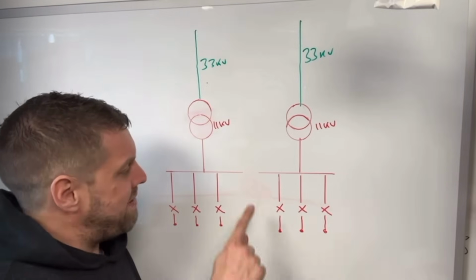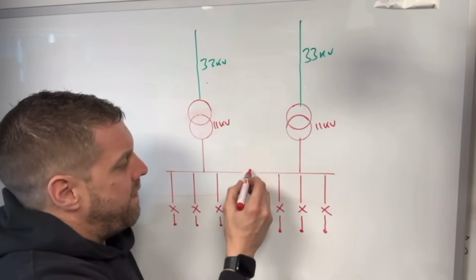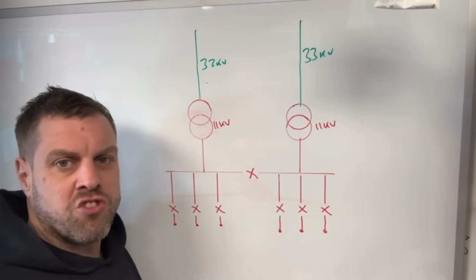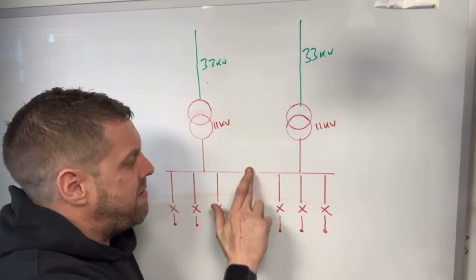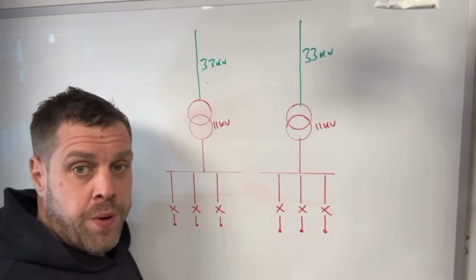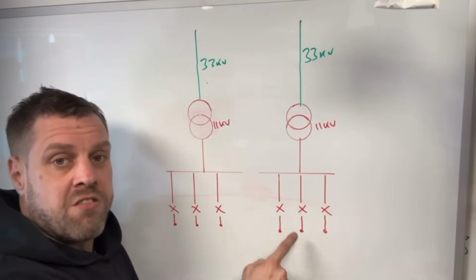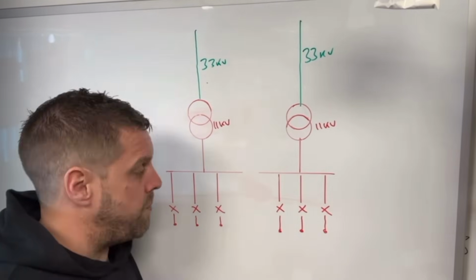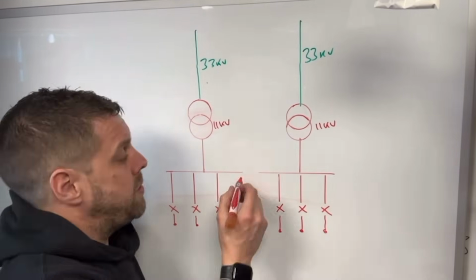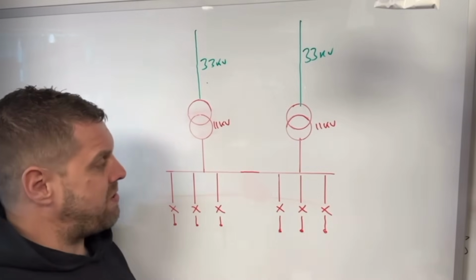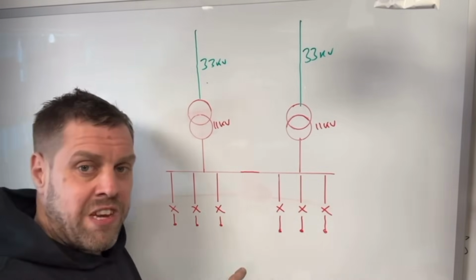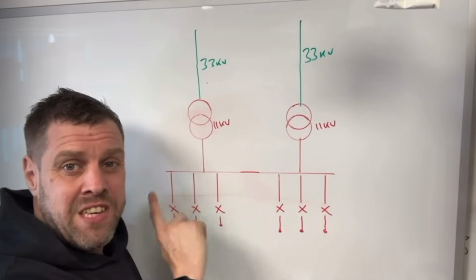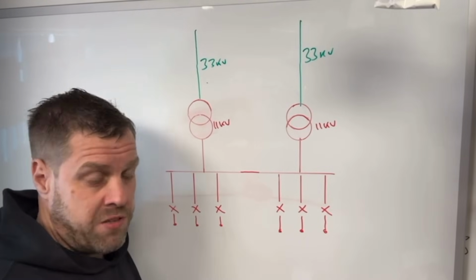However, it has this bit called a bus section here, and the bus section looks like that, just a switch in the middle. What you can do is leave the bus section open, therefore you've got three circuits and three circuits fed from different transformers. Or you can connect it together, in which case you've got all 6 circuits being fed, sharing the load off both transformers.